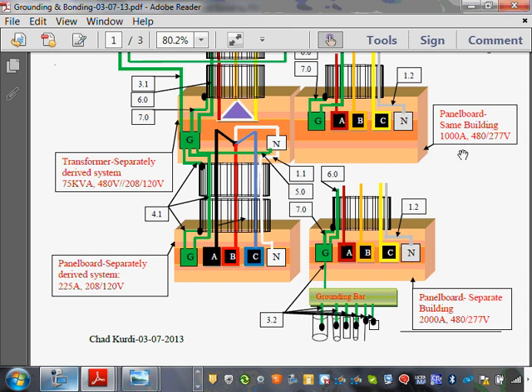So what adds up here is right here you drive a ground rod for the transformer, and you don't pull that one all the way back. You drive the ground rod right here, and then the whole system is bonded together through the equipment grounding conductor. That's if you are outside. That's typical for generators, for the generators that we do. We're coming to the generator in a second. Any comments, guys, for separately derived systems?